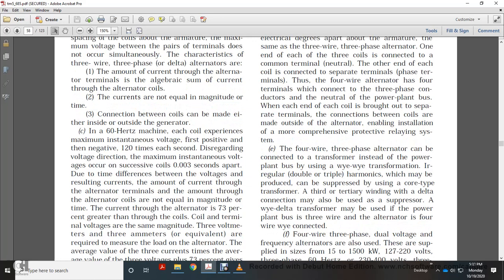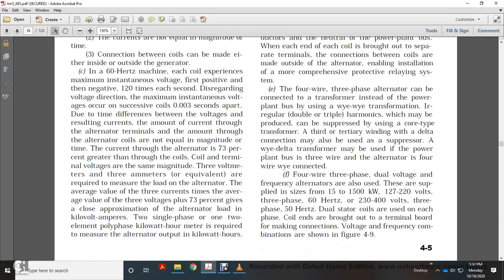Can the 4 wires of the 3-phase alternator be connected with the transformer instead of the power plant bus? Using Y-Y transformation can be irregular, with double or triple harmonics, which may be produced and need a suppressor. Even with the core type of transformer, a tertiary winding in delta connection may also be used as a suppressor. A Y-delta transformer may be used with the power plant bus, 3-wire, with the alternator with the 4-wire connection.